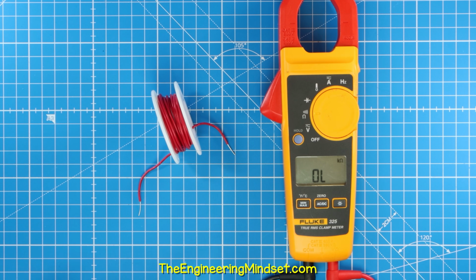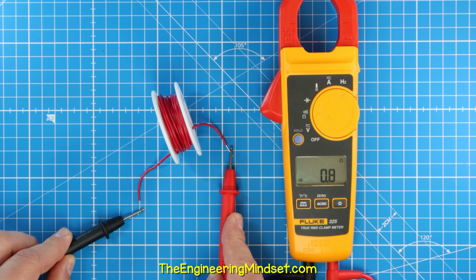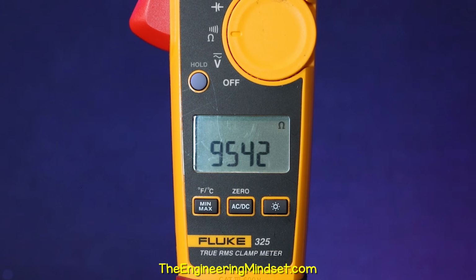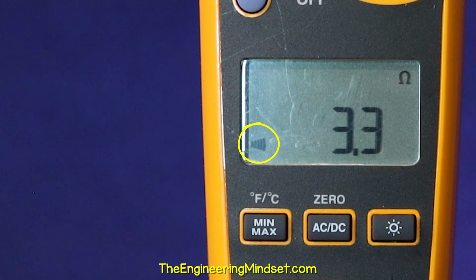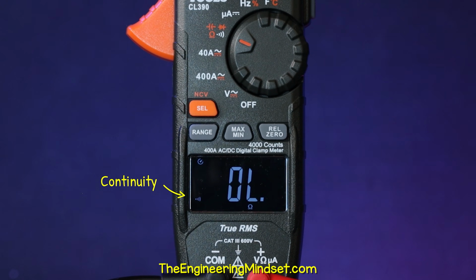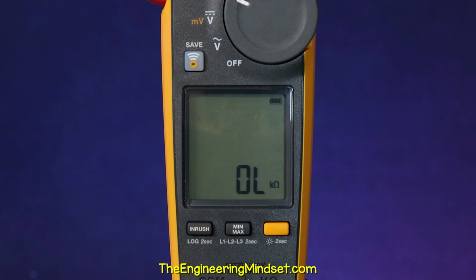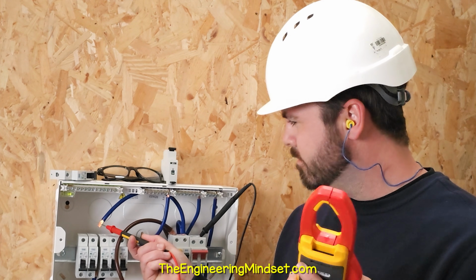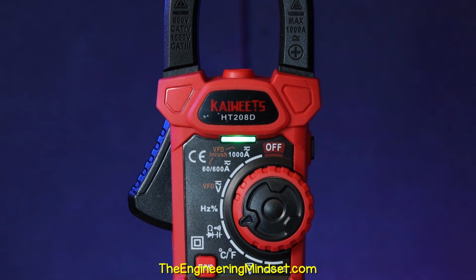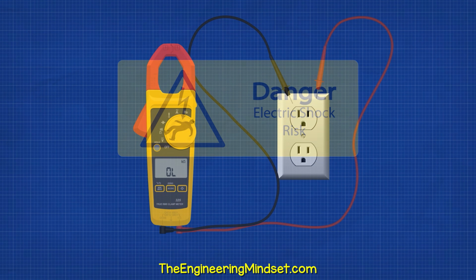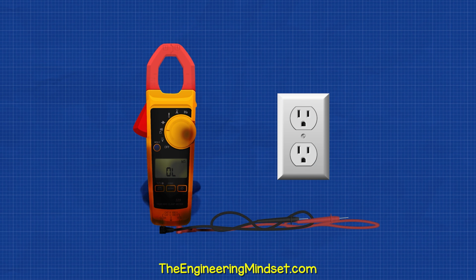It will also tell us the resistance, but this is usually close to 0 for wires. When we complete a circuit, a small symbol might appear, although some meters show this continuously to indicate the function which is selected. The entire screen illuminates on this Fluke meter, which is very useful for noisy environments. Other meters like this have an indicator light built in. Do not attempt to check continuity of an energized circuit.